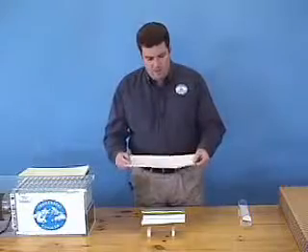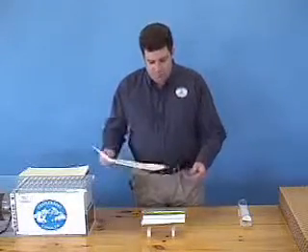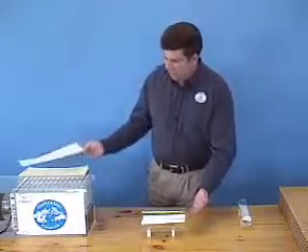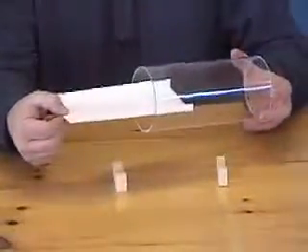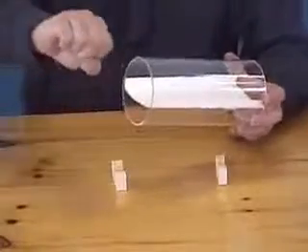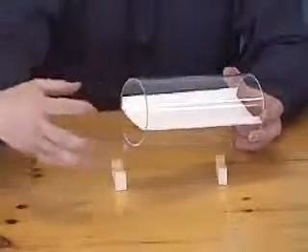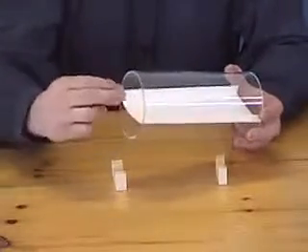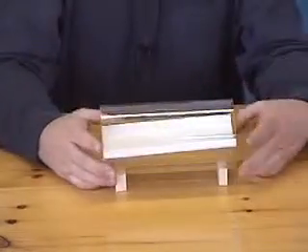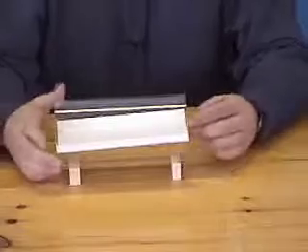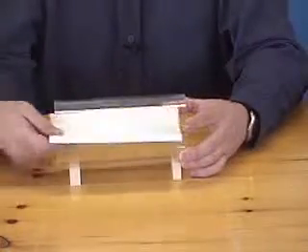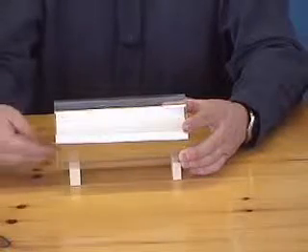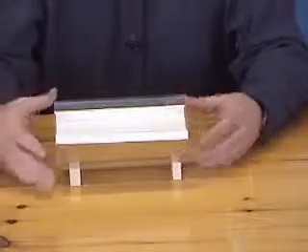Now imagine mounting this plastic-coated paper in the middle of a long insulated tube, much longer than you have here. Then imagine wetting the paper side with water and blowing air through the tube. The air on the wet side is going to absorb moisture until it reaches the wet bulb temperature. That process will pull heat away from the plastic, which will in turn pull heat away from the adjacent airstream.